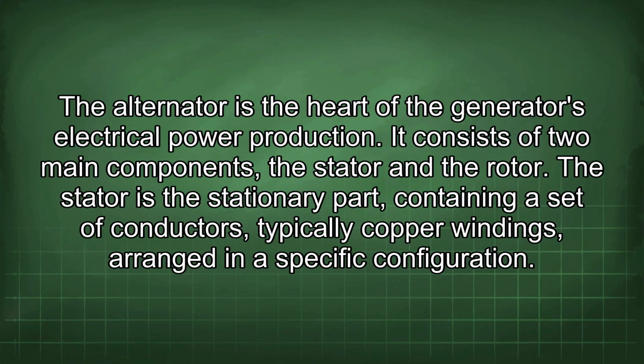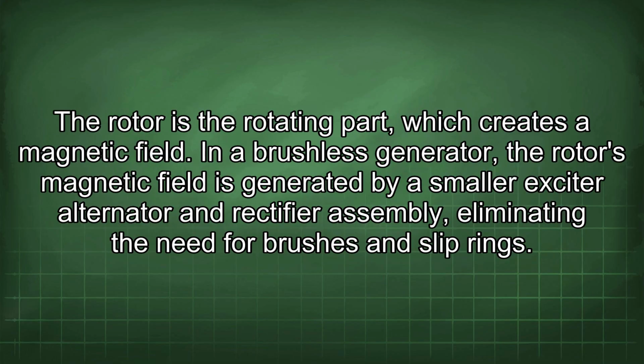The alternator is the heart of the generator's electrical power production. It consists of two main components, the stator and the rotor. The stator is the stationary part, containing a set of conductors, typically copper windings, arranged in a specific configuration. The rotor is the rotating part, which creates a magnetic field. In a brushless generator, the rotor's magnetic field is generated by a smaller exciter alternator and rectifier assembly, eliminating the need for brushes and slip rings.